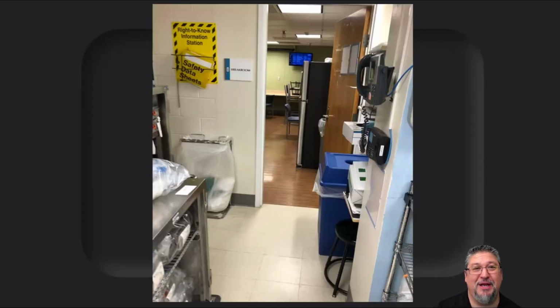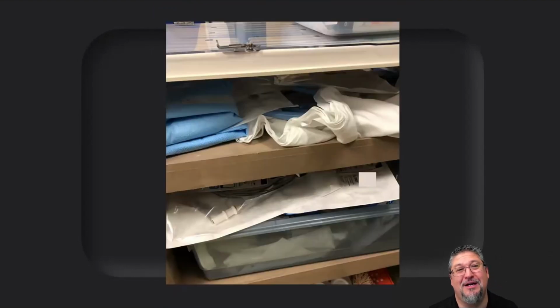This was a decontamination area, and you can see that there is a door from the decontamination area into the break room. And this is an audit that we came in and did at Healthmark. But when we came in, we saw that you could see right into the break room from the decontamination area. Pretty clear red flag that we've got some airflow issues going on here and that there's risk of contamination. I also wouldn't want to eat in that break room.